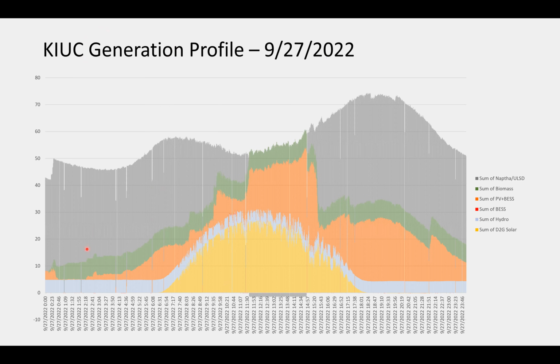And you can see by the color coding, I tried to match it up with the type of source it was. So you've got your yellow, which is your direct to grid solar here that we do measure. This is predominantly our major solar farms that we have on the island, which are two 12 megawatt solar farm nameplate. We've got a 6 megawatt direct to grid solar and another about 1 megawatt. So the combination of that is seen here in yellow. In blue on top of that is the hydro of what it was doing that day.